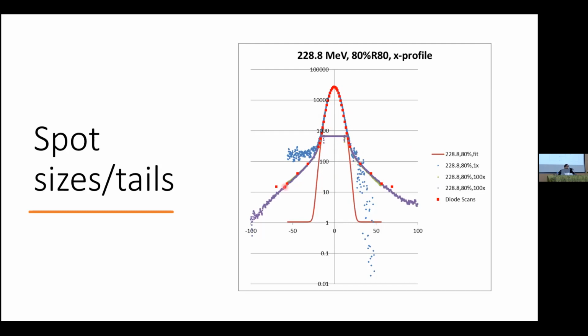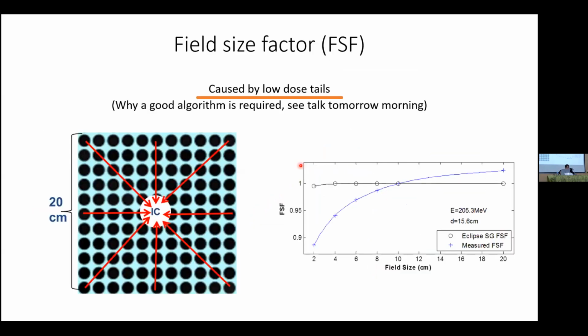The reason this is important is because you have to characterize these tails. Whatever system you put in, this region down at 2% and below is going to be very unique to your system. Of course, your spot shape, your sigma and so on are going to be unique, but depending on what the beam goes through, what it hits in the nozzle, how the monitor chambers are made, how the spot position monitors are made, all these different things add to these wide tails. And you think, oh, these wide tails, that's no big deal. Again, 1%. But when you're doing spot scanning, you've got to remember the fill.